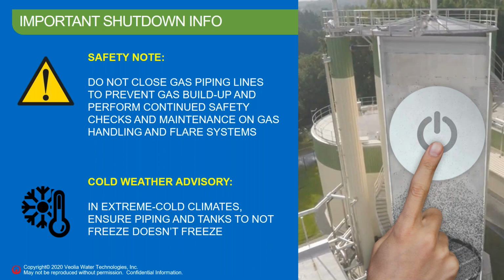And again, if you're going to shut down at this time of year, you can freeze. I think in the 40 years that I've been doing this, every Christmas holiday, somebody calls that they have frozen a line because it wasn't heat traced or insulated properly, or something happened like that during this upcoming Christmas shutdown. So be really careful with that. Make sure that your heat trace is all on, and that all the insulation is put back after you've torn it off for some reason during the year, so that the lines don't freeze when there's not warm water going through them. Really important thing to do.